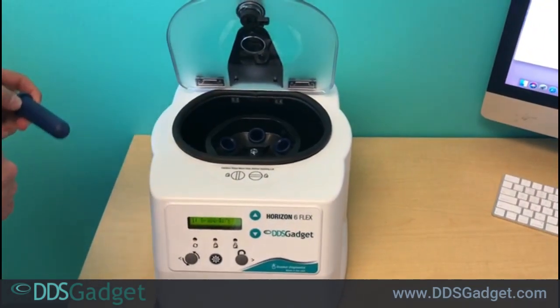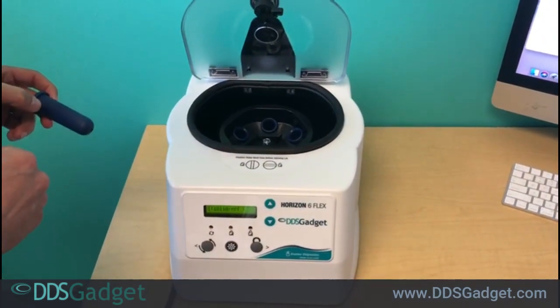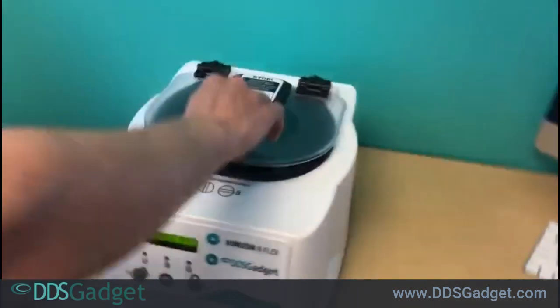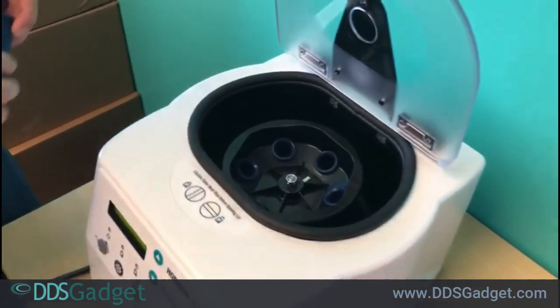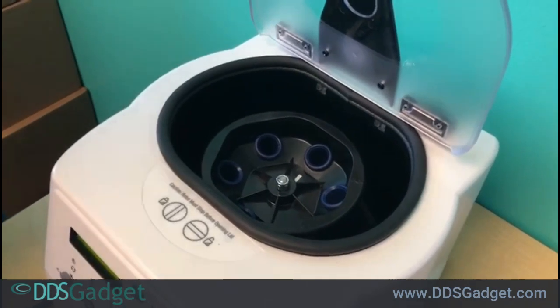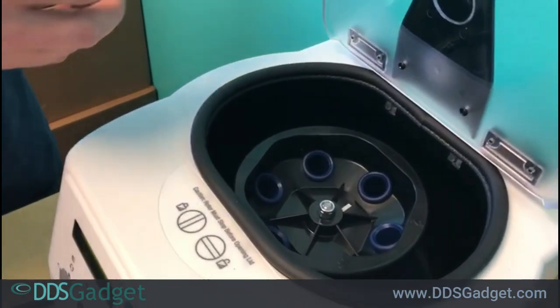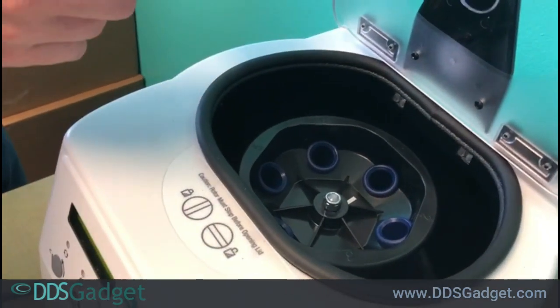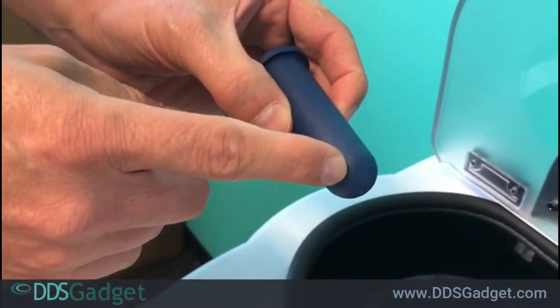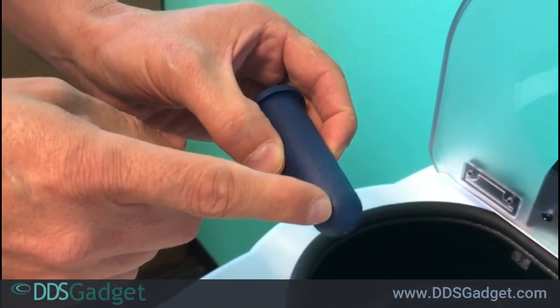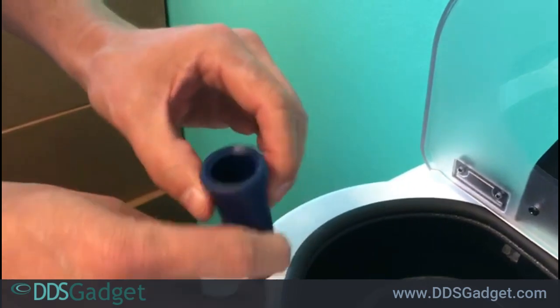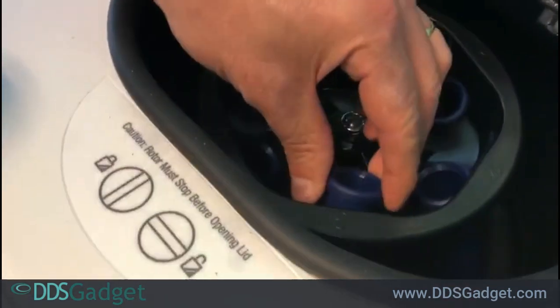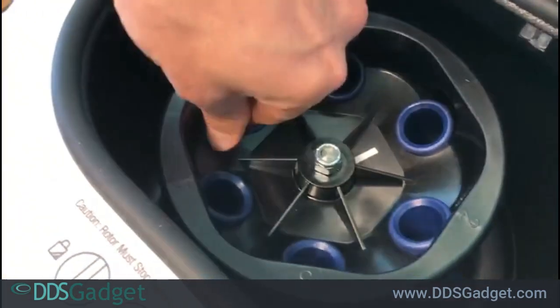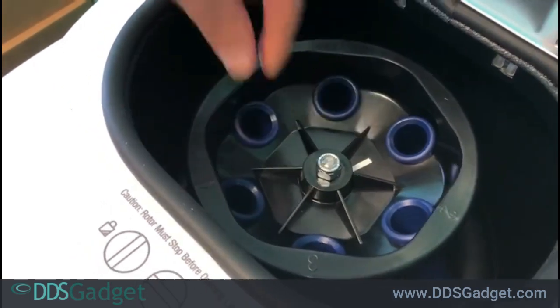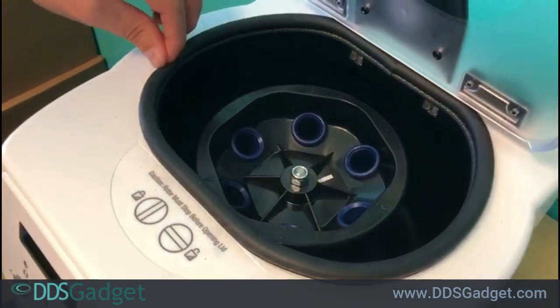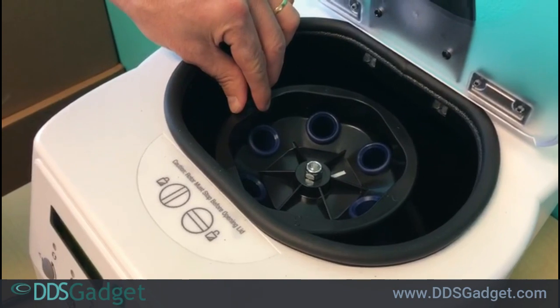This video is about preparing the centrifuge and choosing your cycle. So after unlocking the centrifuge, you can then place the tubes that you just drew with blood into the centrifuge. Please remember to always use the blue tube holders in the centrifuge prior to placing in any tubes. The blue tubes are the ones that came with your centrifuge, and you can see how they're placed inside the centrifuge. These are very, very important. They hold the tubes that you'll be using during the spinning cycle.